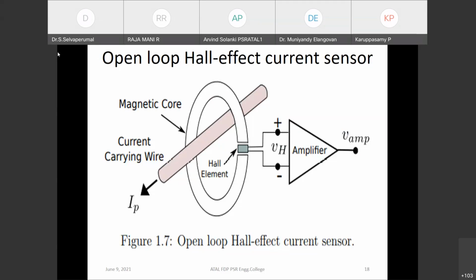Okay. So the output voltage of the Hall element consists of two components, common mode, that is Vcom, and differential mode Vh. So only Vh responds to the changing magnetic field. The magnitude of Vh is of the order of millivolts even for a large current. A differential amplifier with high CMRR is required at the output of the Hall element to bring the amplified output voltage Vamp into proper measuring range. So normally operational amplifiers are used to amplify Vh. In high precision applications, instrumentation amplifiers are used, right? So the configuration of the sensor shown in the slide is known as the open loop Hall effect current sensor, right?